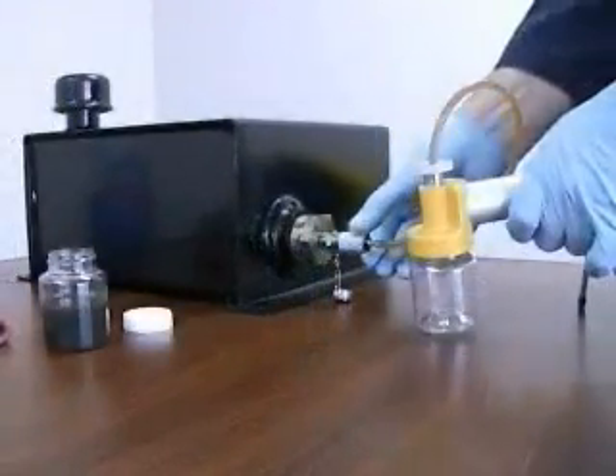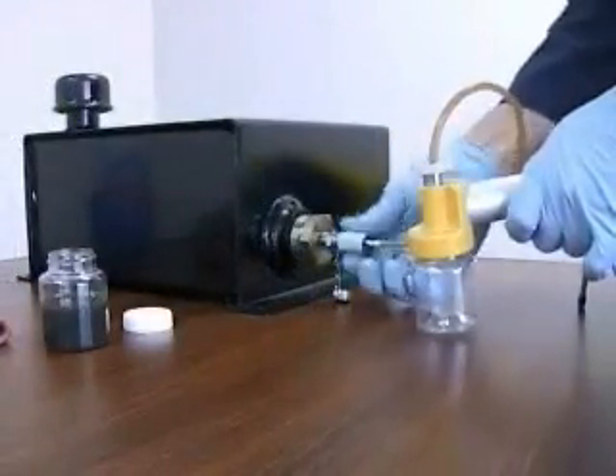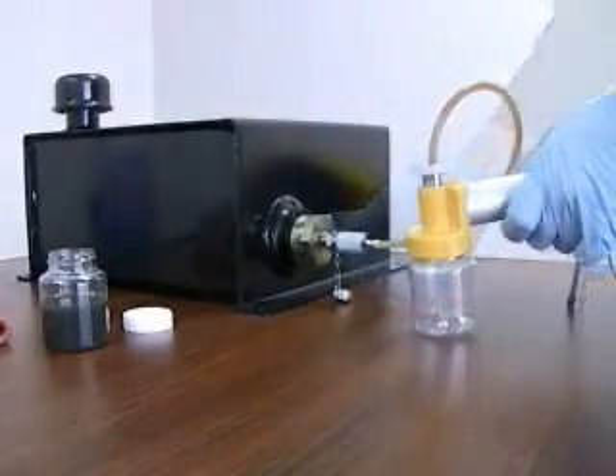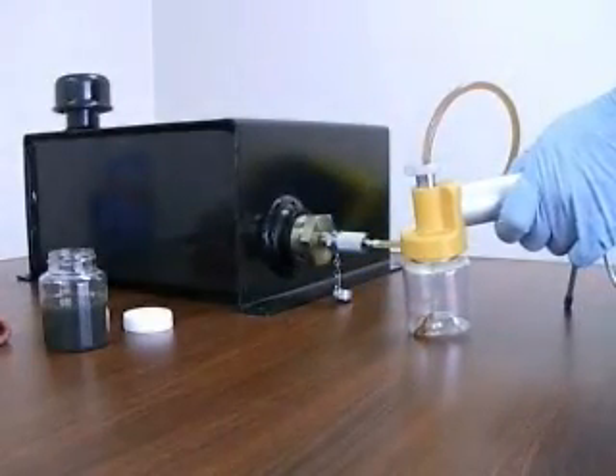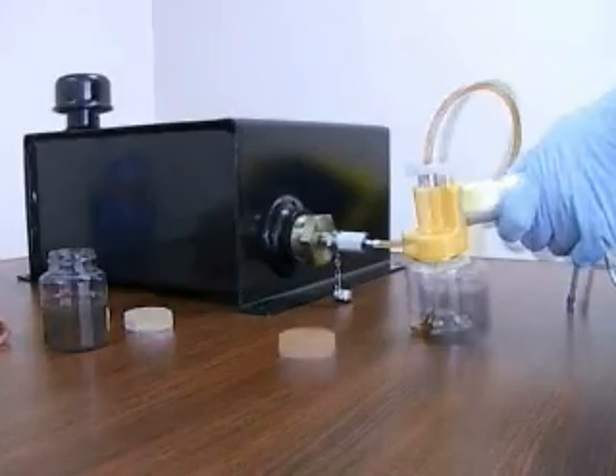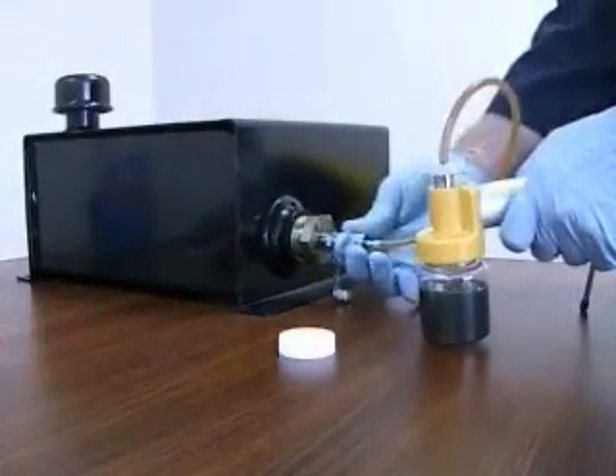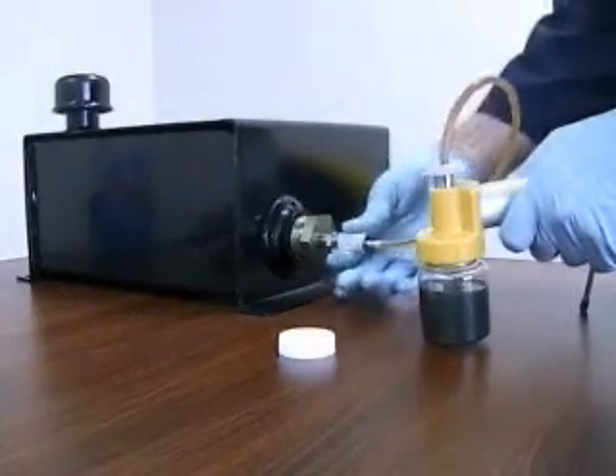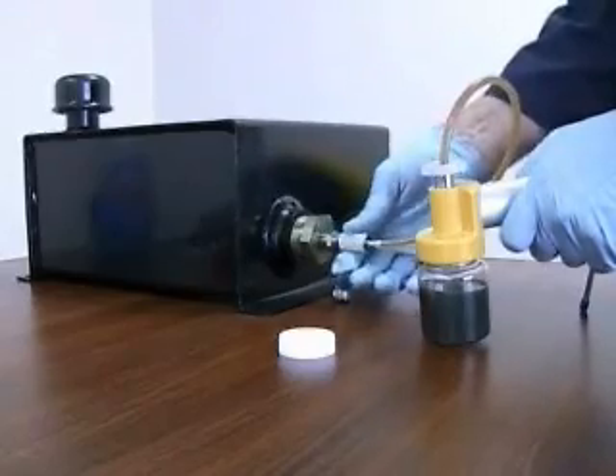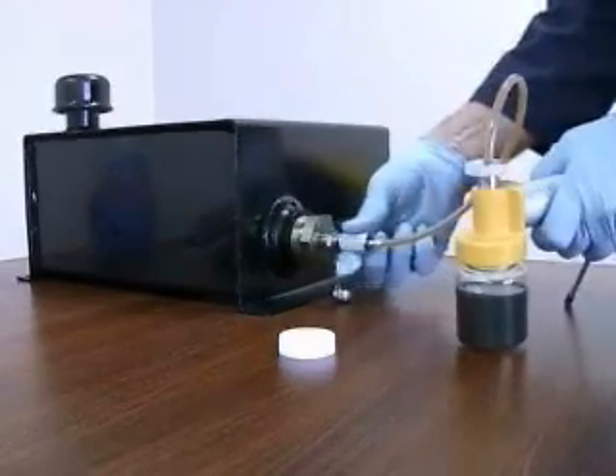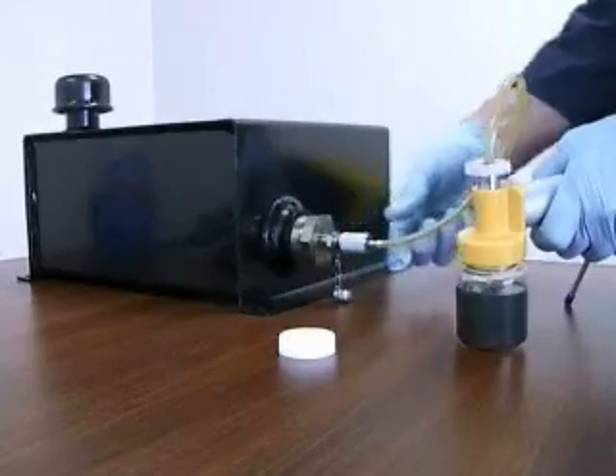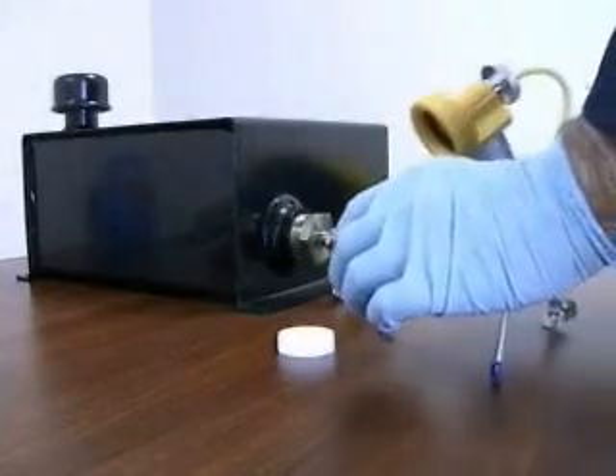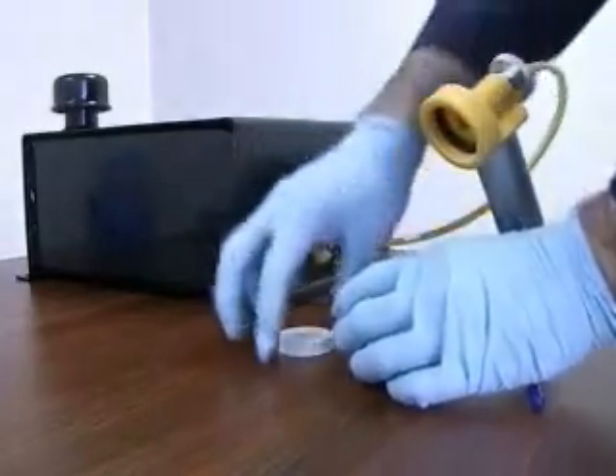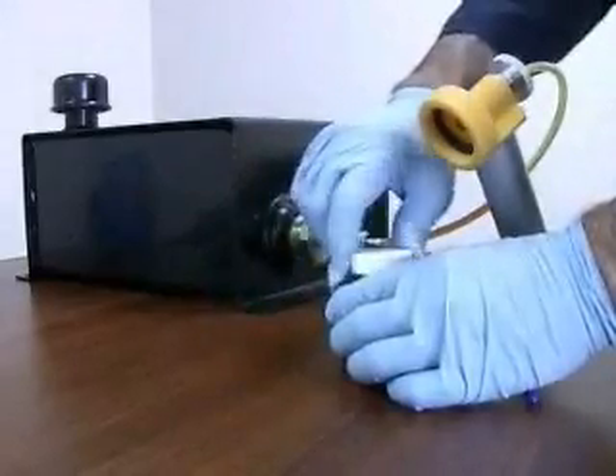To draw the lab sample, retighten the probe 2 turns on the valve. Pull this vacuum plunger several times to restart the flow. After the required sample is drawn, unthread the probe 3 or 4 turns, which will stop the flow and help evacuate the line. Do not fully remove the probe. Cap the lab sample bottle, label it, and send it off for analysis as soon as possible.